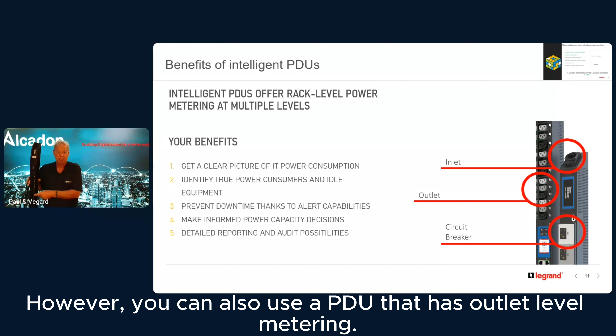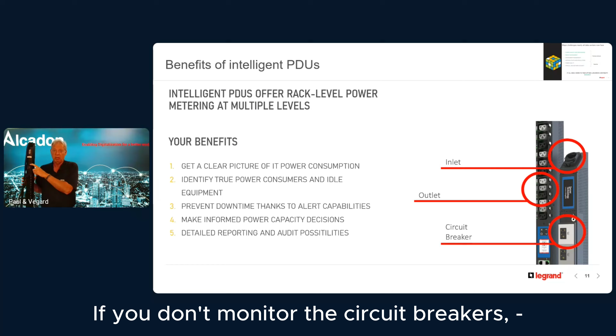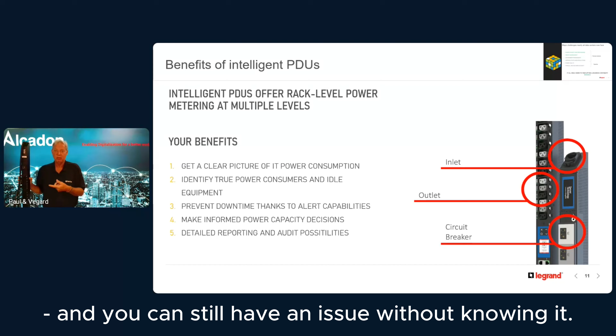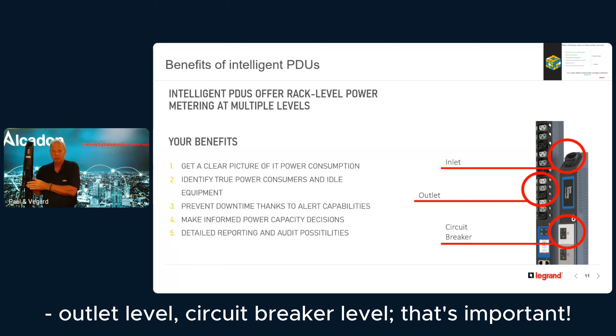If you buy a PDU, be aware that some PDUs have a circuit breaker. And circuit breakers need to be monitored also. If you don't monitor the circuit breakers, you are missing part of the information and you can still have an issue without knowing it. So measuring on inlet level, outlet level, circuit breaker level. That's important.